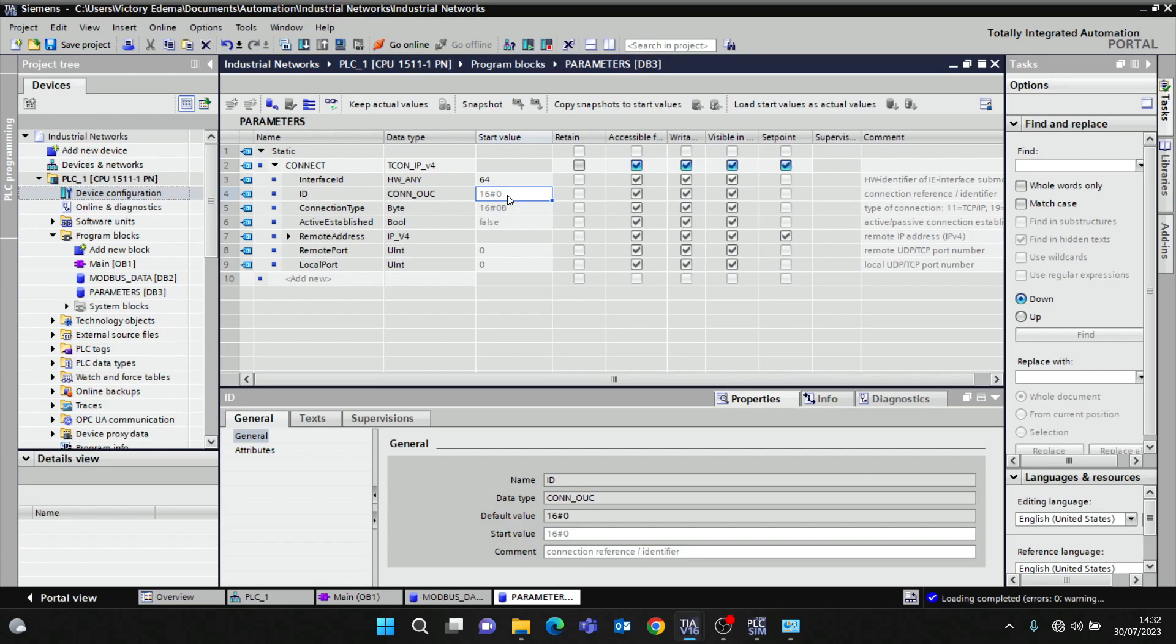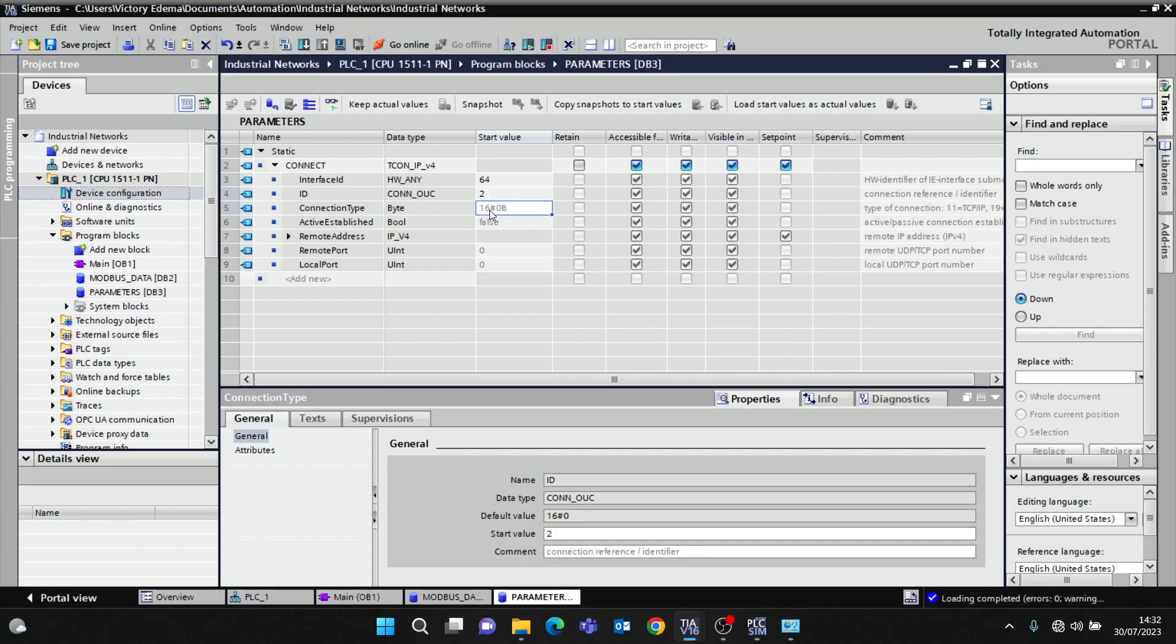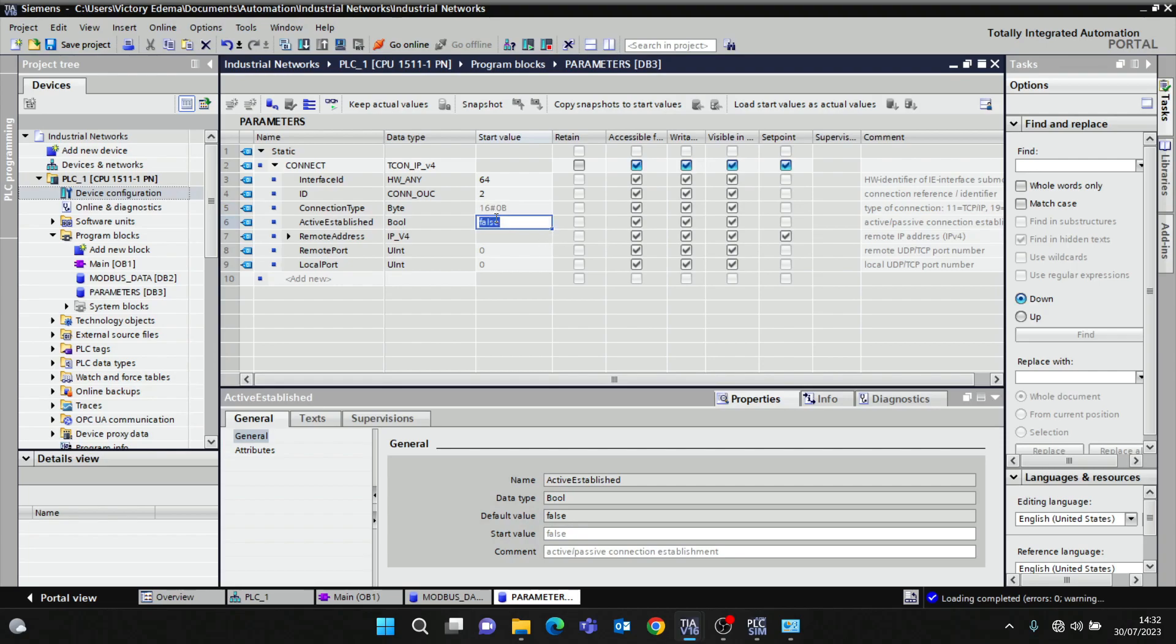ID - you can give it any number you want. I want to use 2, so this would be the connection reference or identifier. Connection type: 11 is TCP/IP, 17 is UDP. 16#0B - B is 11, so we're using TCP. Active established - I want it to be active.